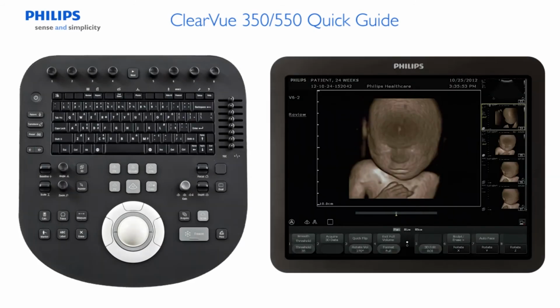This section will demonstrate the Threshold Smooth Quick key. Note that this is a dual-function Quick key. Press the Quick key to cycle between Threshold and Smooth. Threshold is used to remove low-level echoes from the volume. Press the Smooth Threshold Quick key to display Threshold. Turn the Threshold Quick key to increase or decrease the level of threshold.